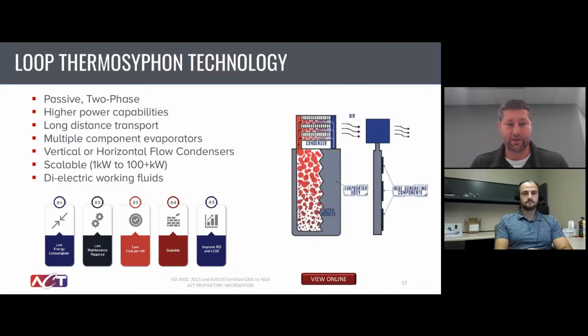So that's kind of the heat pipe side of things. Another passive two-phase solution, kind of a variant off heat pipe technology, is thermosyphons and then loop thermosyphons. A thermosyphon is the name for a gravity-assisted heat pipe. So in those cases, you do not need a wick structure to return the fluid. You're relying on gravity to return the fluid. And in those cases, it could be very similar.